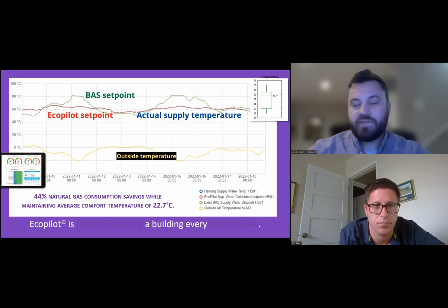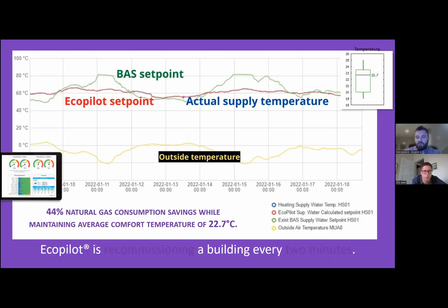What Ecopilot's doing is it's calculated, alright, we know we have X amount of tons of concrete in this building, we know we've got people coming in today, we know there's machinery in the building such as computers, lights, things like that. There's a lot of free energy that we can capture, so we don't really need to ramp up the heating system as much as what the BAS is typically accustomed to doing. As you can see, there's a slight hump in the red line just below the green, and it's saying, okay, that's it. And the building was able to maintain a temperature of 22.7 degrees.